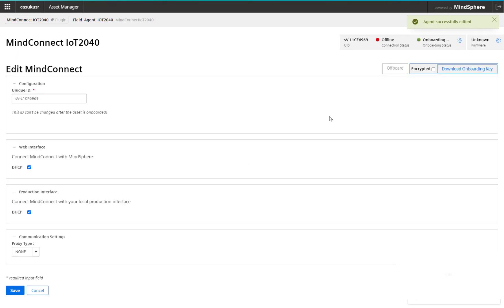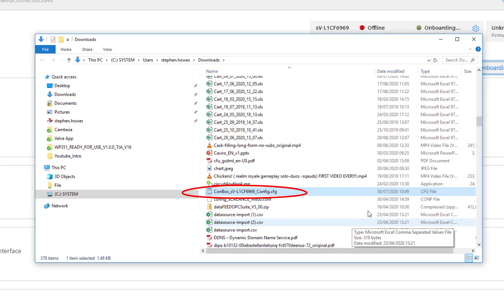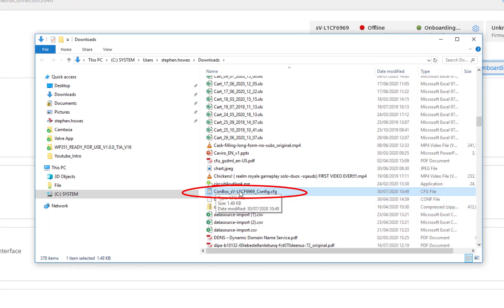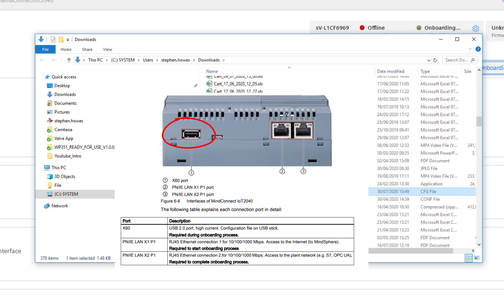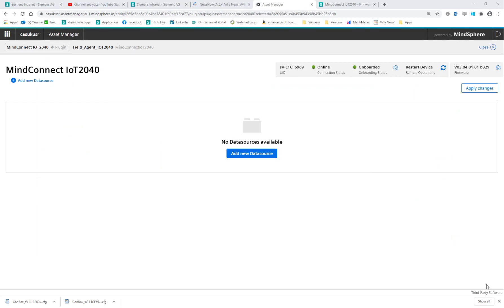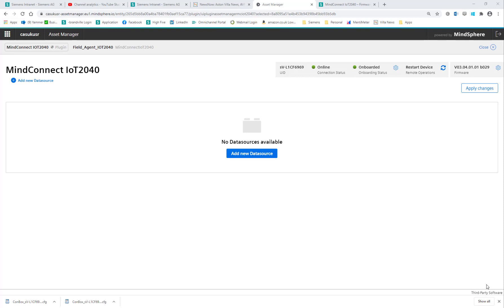Once you have made those changes you can see 'Download onboarding key' — so you need to download the key. This needs to be downloaded to a memory stick, and then you insert that into the device and monitor this onboarding screen. Once you plug the USB memory stick into the IoT 2040 it will go through a sequence of lights, but when it's connected you'll see the three green lights come on. If you go back to your asset you will see the online and onboarded status.